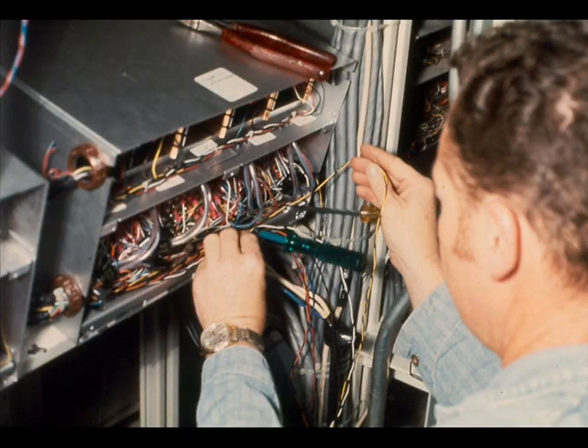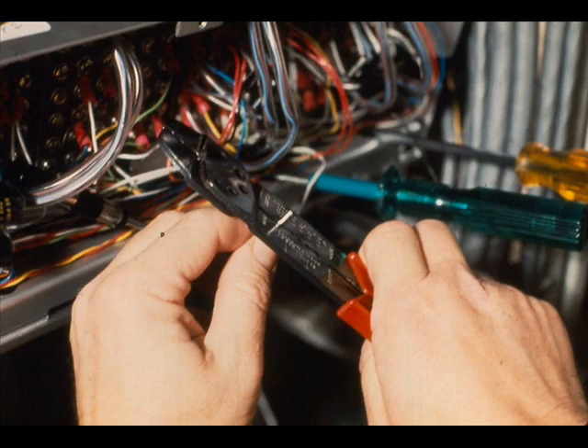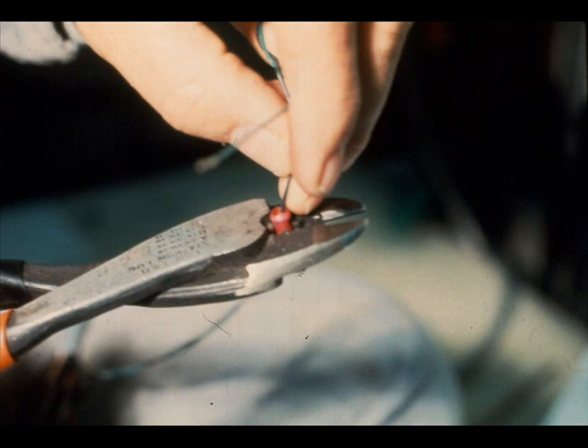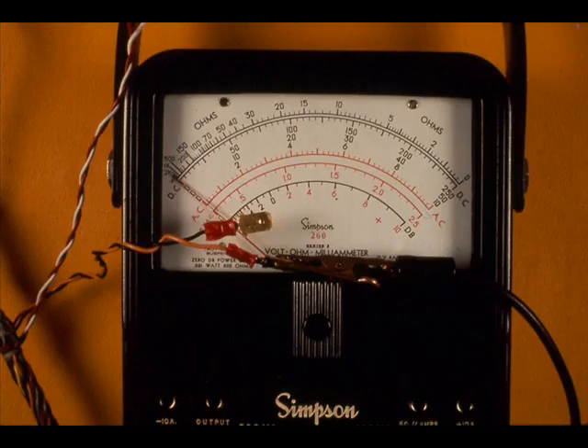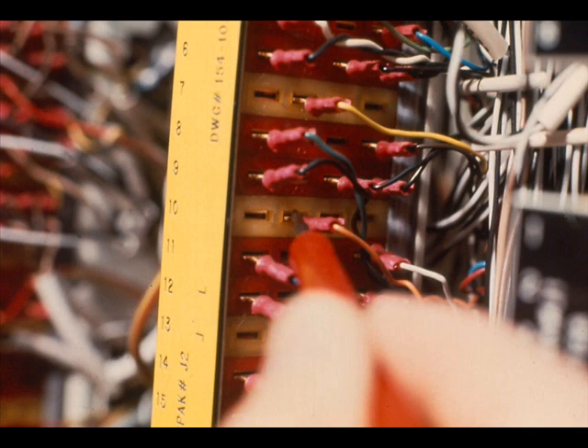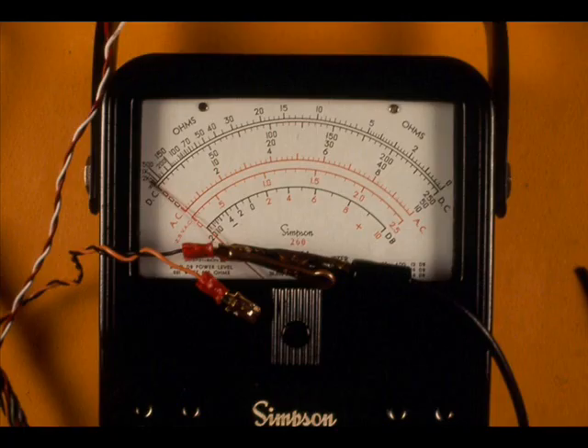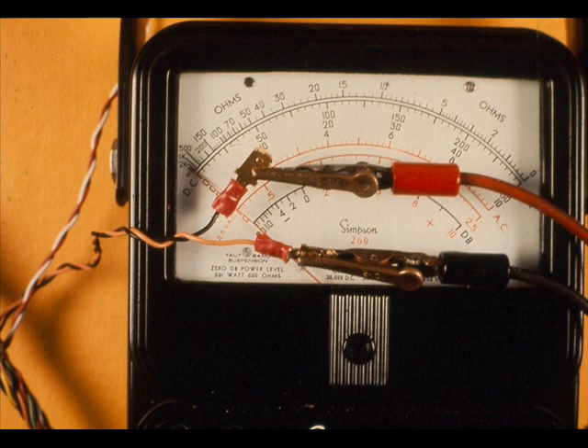Now locate the orange-black and white-red pairs at the controller. Form and attach the lugs to the wires, but do not terminate the wires yet. Verify the continuity of all 4 wires. For instance, attach the buzzer or VOM from the orange wire to ground. Ground TB 256-1, terminal 10C. Check the other wires in a like manner. Check for shorts and grounds.